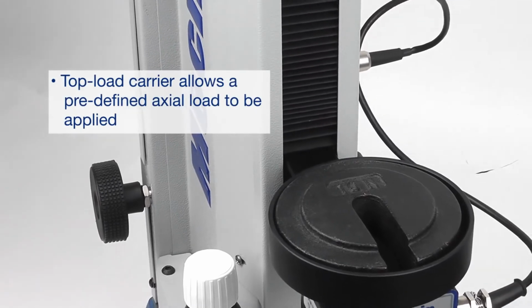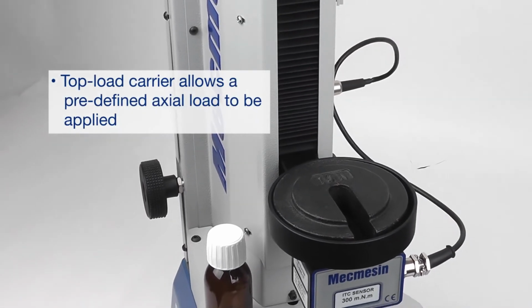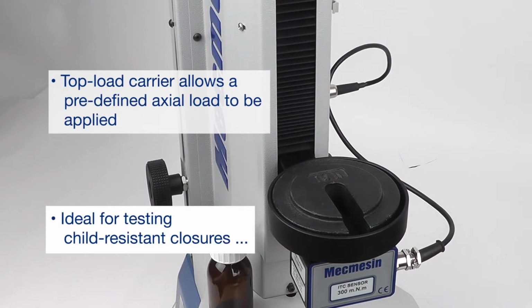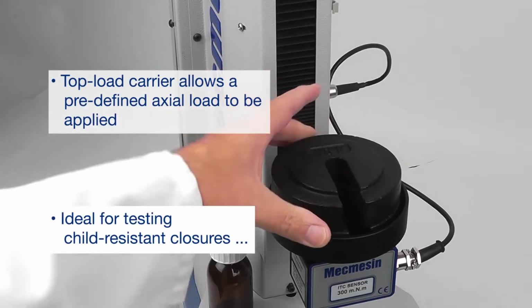The same counterbalance system can also be used to apply constant downforce, which is needed when testing child-resistant closures or luer lock fittings on syringes or other medical devices.